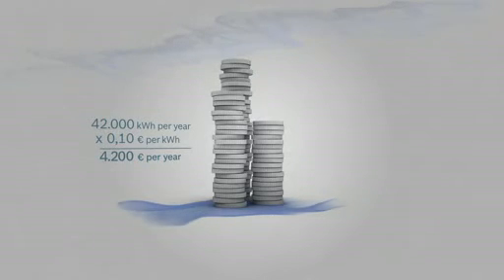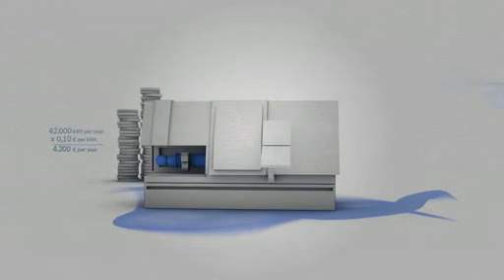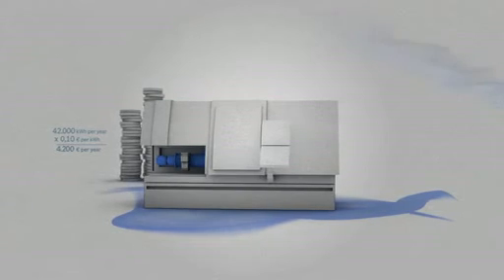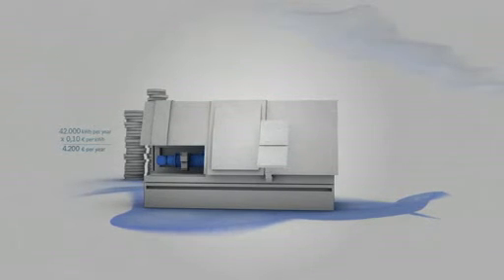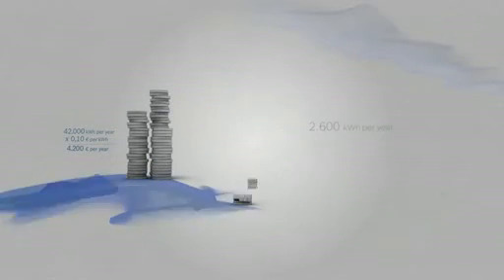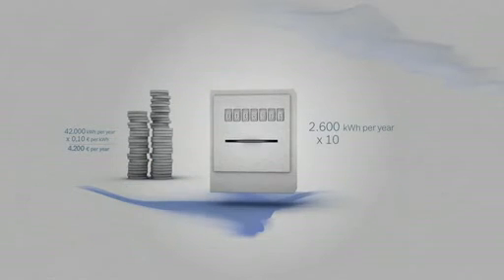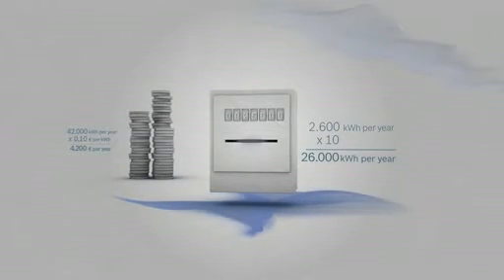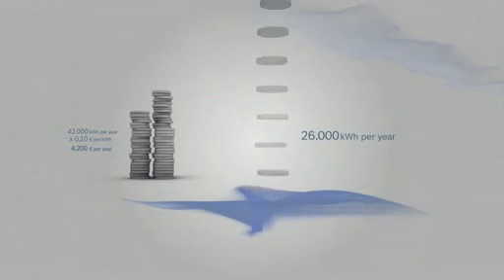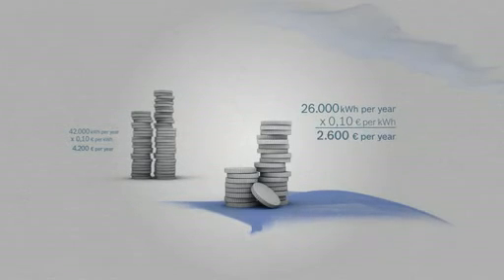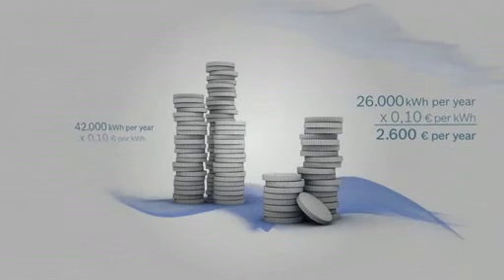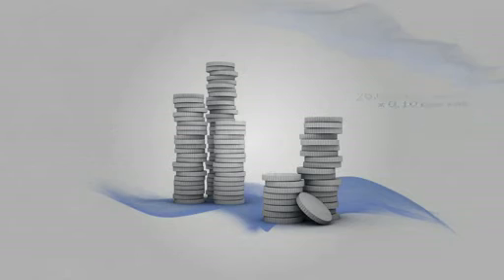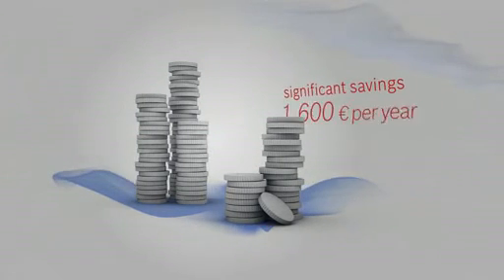Now imagine that your lathes have been enhanced and are now equipped with our variable speed pump drives. One machine would then require only 2,600 kilowatt hours per year. For 10 machines, this amounts to 26,000 kilowatt hours and the significantly lower cost per year of 2,600 euros. Hard to imagine, but this means a savings of 1,600 euros per year, leading to a cost reduction of 40% over conventional drive systems.